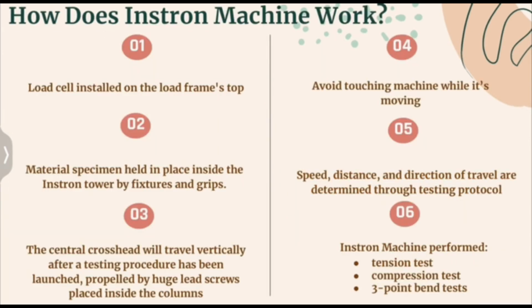How does the Instron machine work? The load cell is installed on the load frame's top, where the material specimen is held in place inside the Instron tower by fixtures and grips. The central crosshead will travel vertically after the testing procedure has been launched, propelled by huge lead screws placed inside the columns. It is advisable to not touch the machine while it's moving. The speed, distance, and direction of travel are determined through the testing protocol.